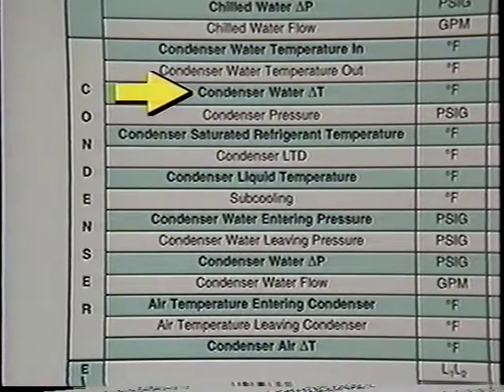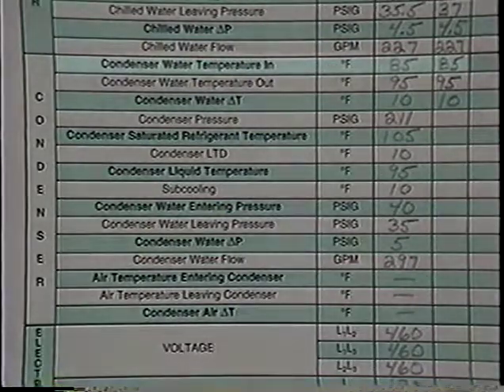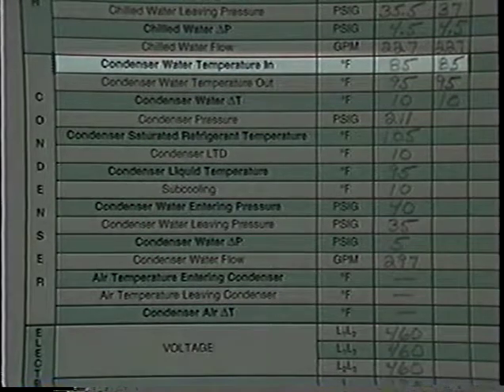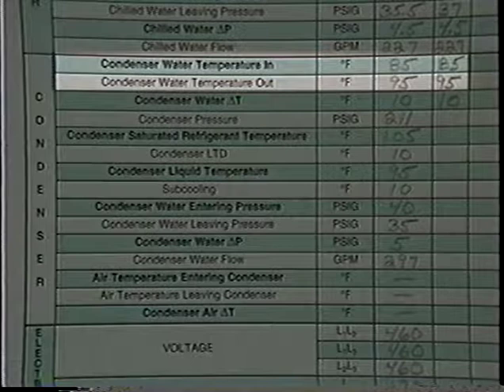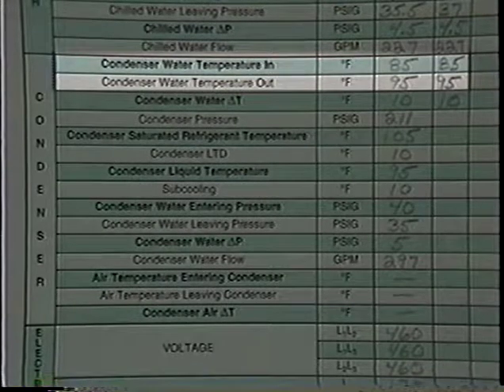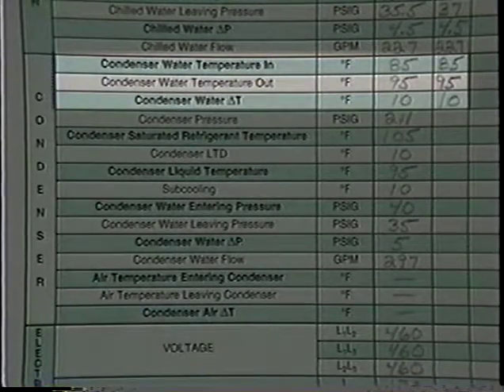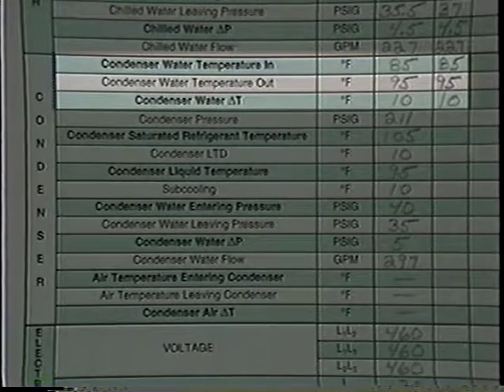Condenser water delta T. Next, we'll find the condenser water delta T. Do this by subtracting the entering condenser water temperature from the leaving condenser water temperature. Condenser water delta T provides an indication of condenser heat rejection.